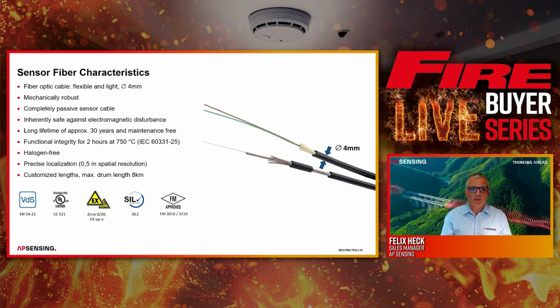Precise location. I measured this already up to 0.5 meter spatial resolution, where we can tell the operators exactly the position where the temperature is located and what is the value of the temperature itself and the propagation of the fire. So if there's one car burning or two cars burning and so on. Very important for the fire brigade. And last but not least, we provide customized lengths for the sensor cable. So if you need 1,350 meters, for example, then you will get this from us, also with pigtails on both ends. So very practical and very convenient for the installation company.